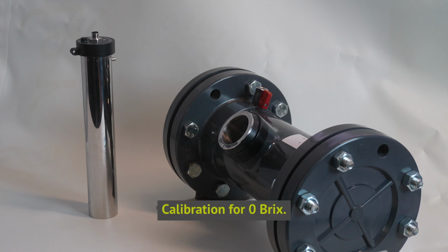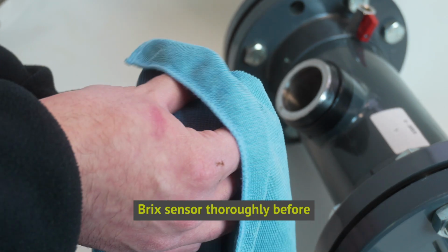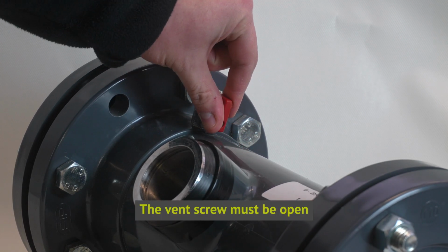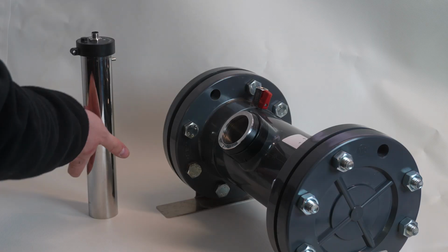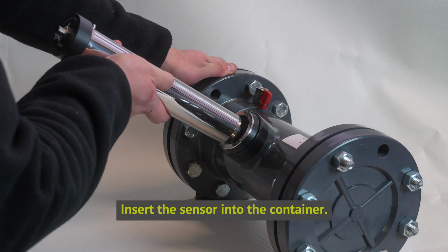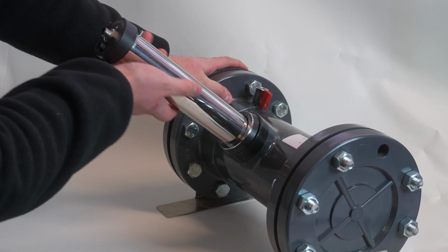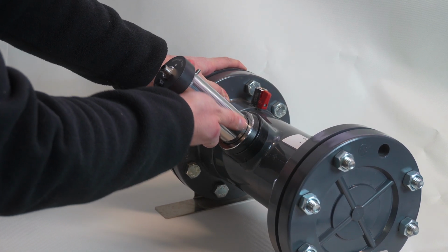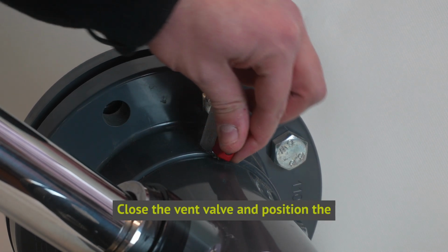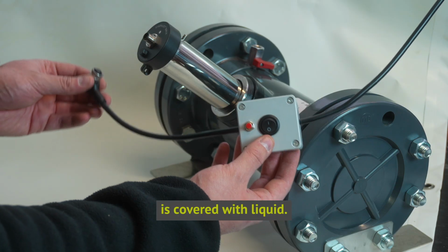Calibration for 0 Brix. Clean the glass surface of the Brix sensor thoroughly before inserting it into the liquid. The vent screw must be open while inserting the sensor. Insert the sensor into the container. Close the vent valve and position the unit so that the prism is covered with liquid.